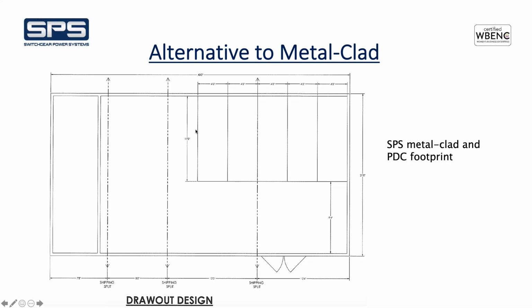So your switchgear was about 11 feet deep. And because the breakers are draw out, you need a large aisle. 38 kV breakers are obviously quite large. And the overall footprint of the PDC was 21 feet, I'm sorry. So because it was 40 by 21, it required us to have multiple shipping splits, and the PDC would have shipped to site in multiple pieces.